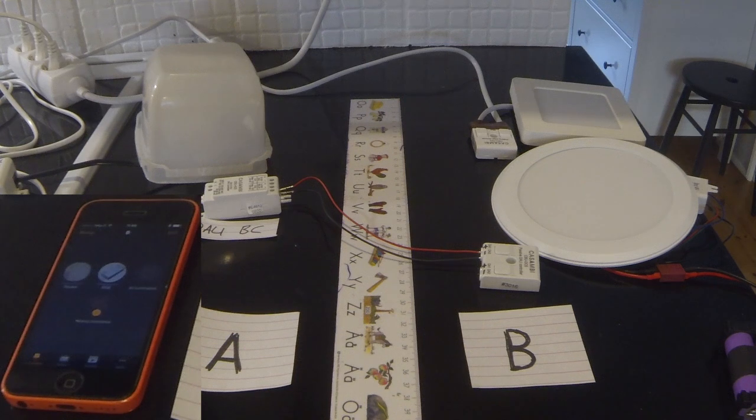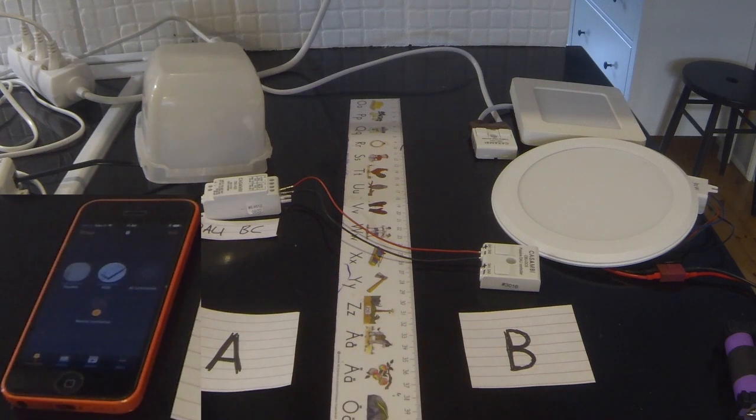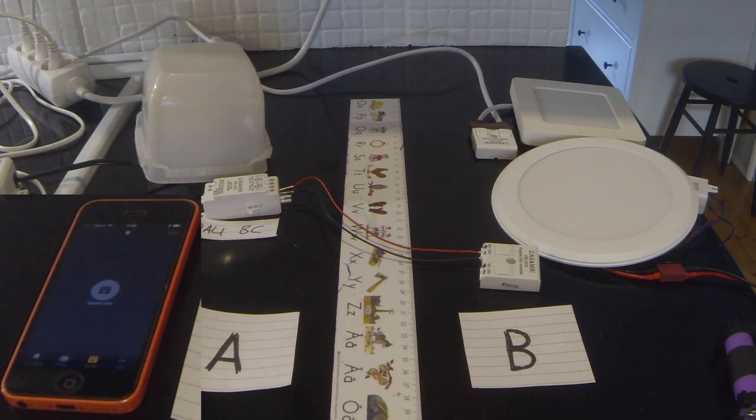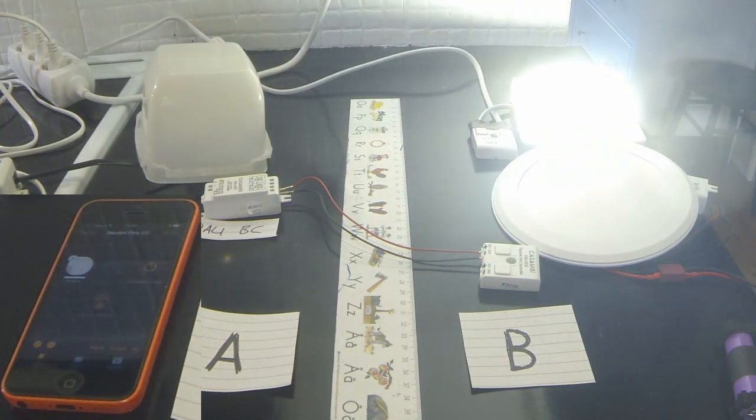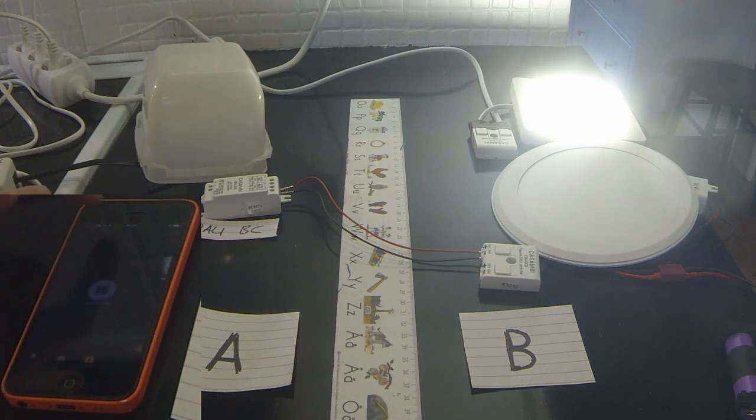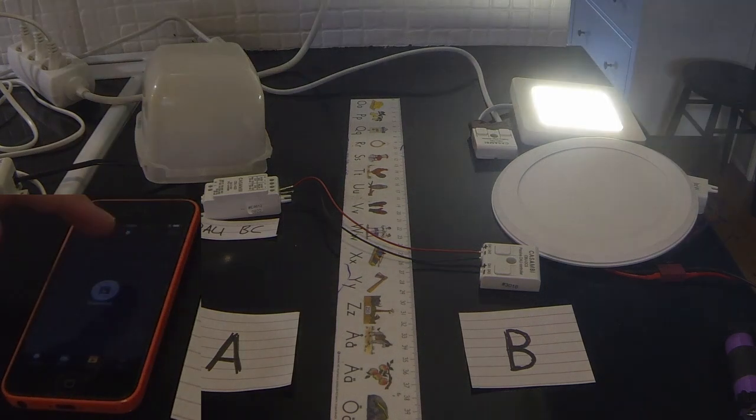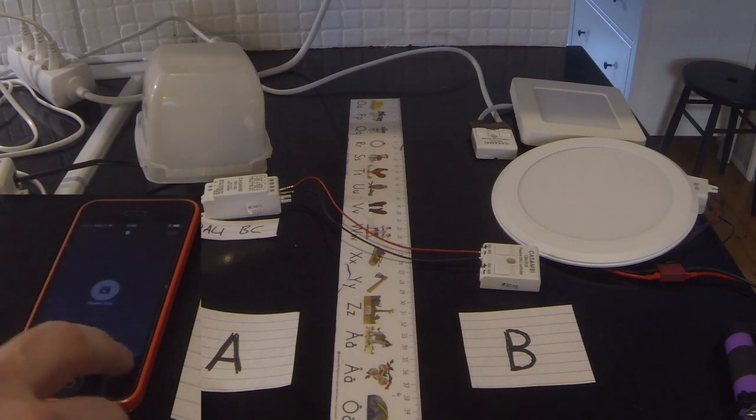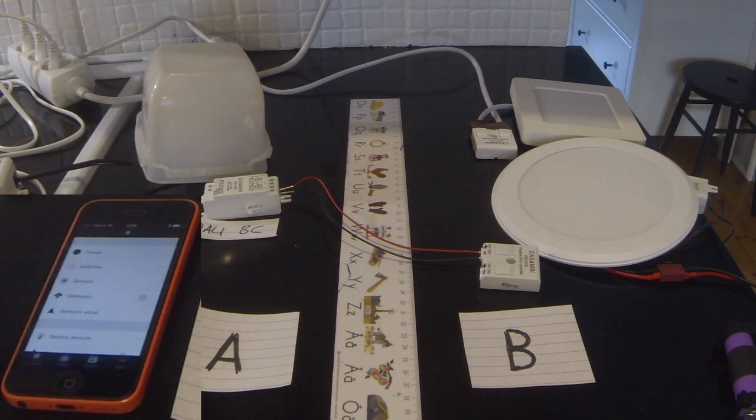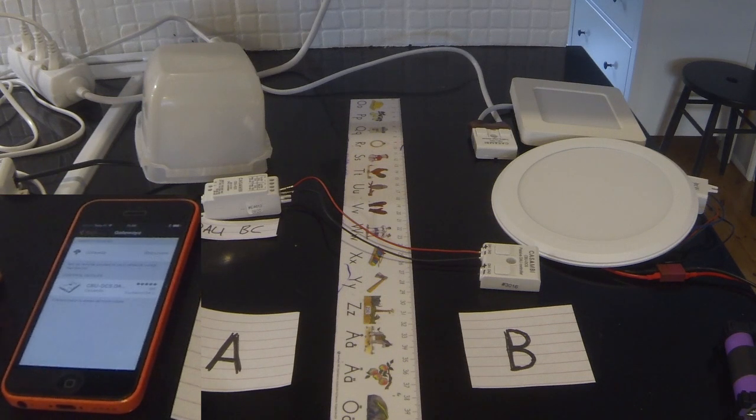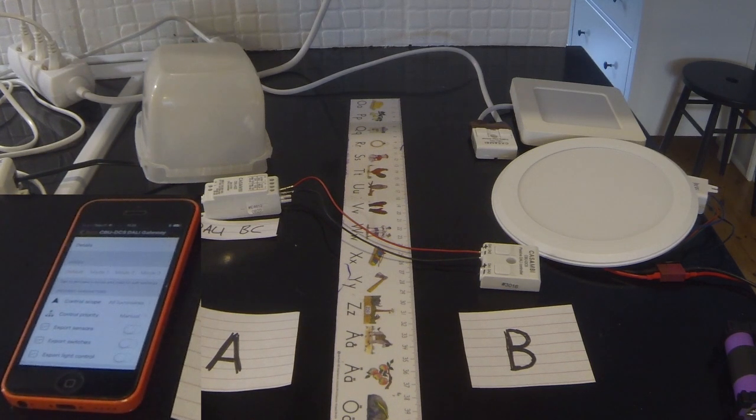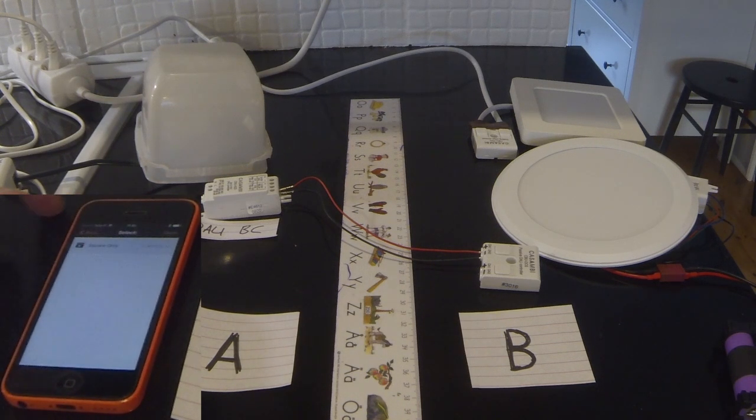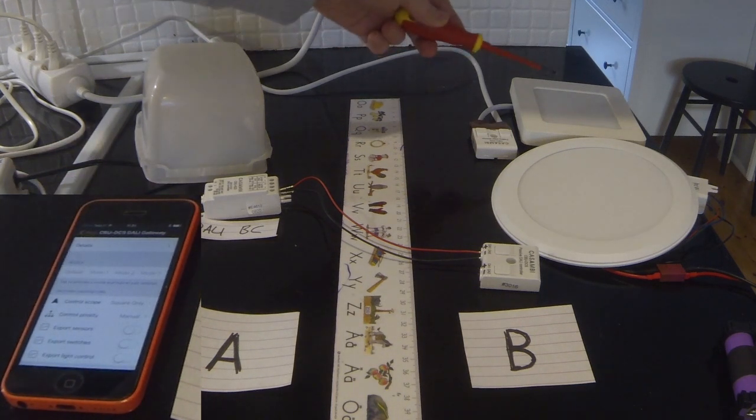Let's presume that when there is presence seen on this device, we only want one single light in network B to come on. So the way we do that is we change what is called the control scope within the DALI DCS controller. Before you do that, you need a scene set up. So what I've done in here is created a scene called Square Only, which controls the square light there at 100%, which admittedly is quite bright. So I'll just turn it on and back off. If we then go to more, the DALI DCS gateway is under the gateways tab as you saw earlier. I'll select it. And what I'm now going to change is the control scope. So by default it says all luminaires, but I'm going to change that to this scene called Square Only, which as you know only contains the square light here.